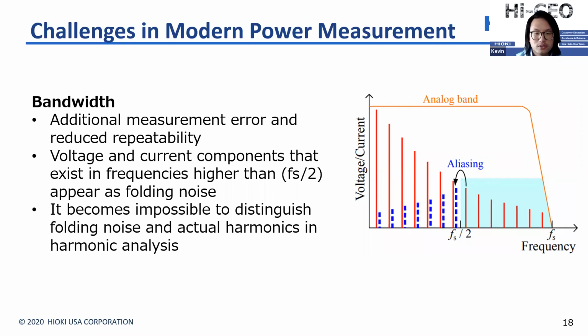We have a graph here that shows the relationship between the sampling frequency and analog band in a typical power analyzer. We see that in similar instruments, voltage and current components exist in frequencies higher than the sampling frequency. This will appear in the low frequency domain as folding noise, also known as aliasing. Our measurement targets include frequency components across a broad band, and sometimes it becomes impossible for us to distinguish between the folding noise and the actual harmonics. All of this means that we have additional measurement errors and reduced repeatability, so it's more likely for us to detect false harmonic components.